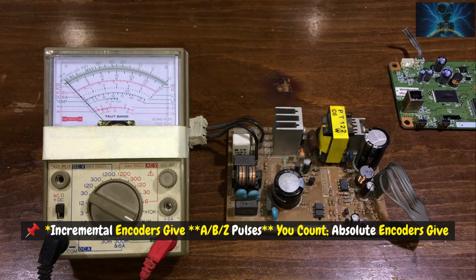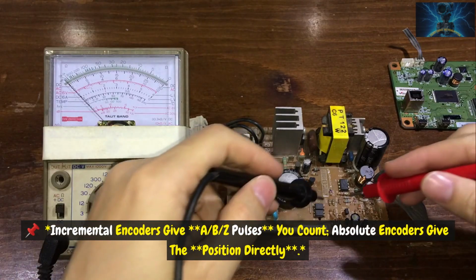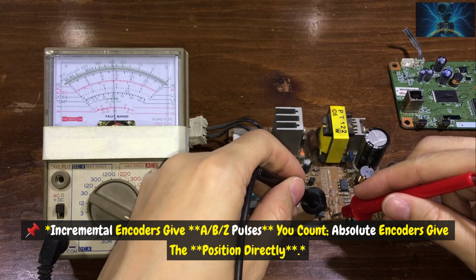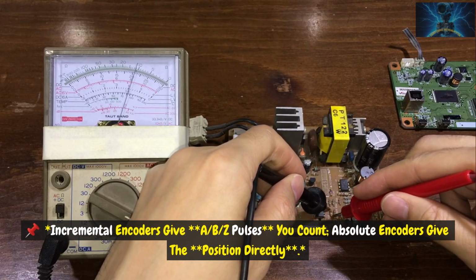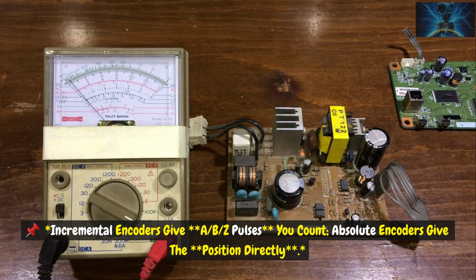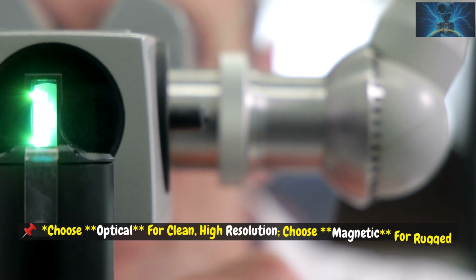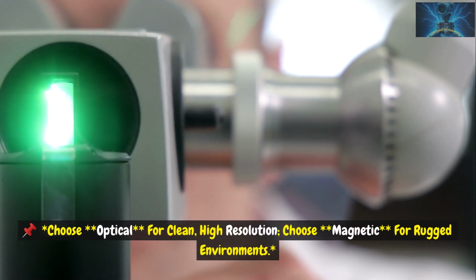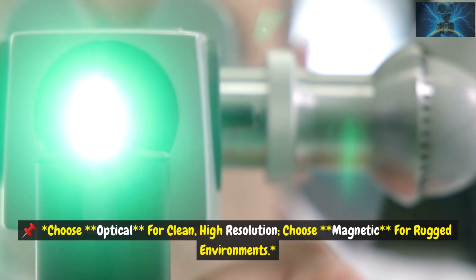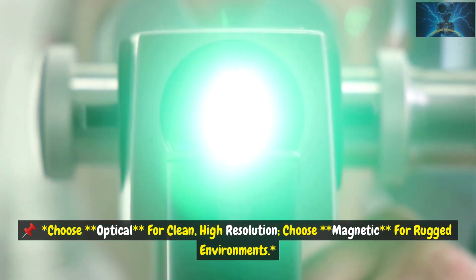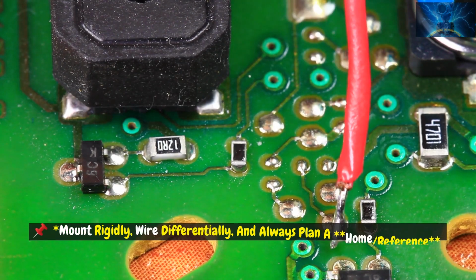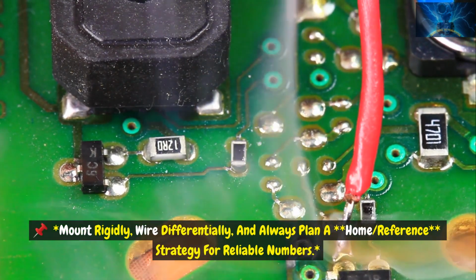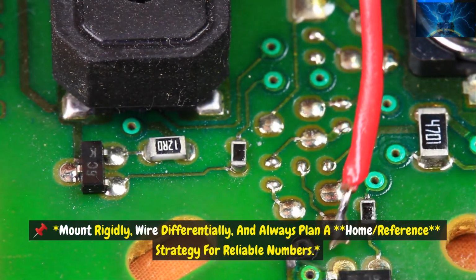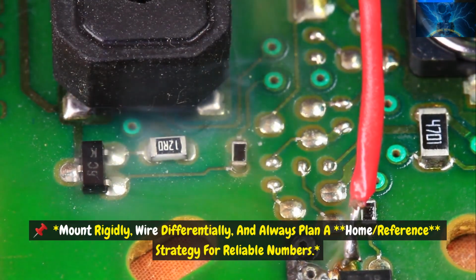Incremental encoders give A and B pulses; you count. Absolute encoders give the position directly. Choose optical for clean, high resolution. Choose magnetic for rugged environments. Mount rigidly, wire differentially, and always plan a home reference strategy for reliable numbers.